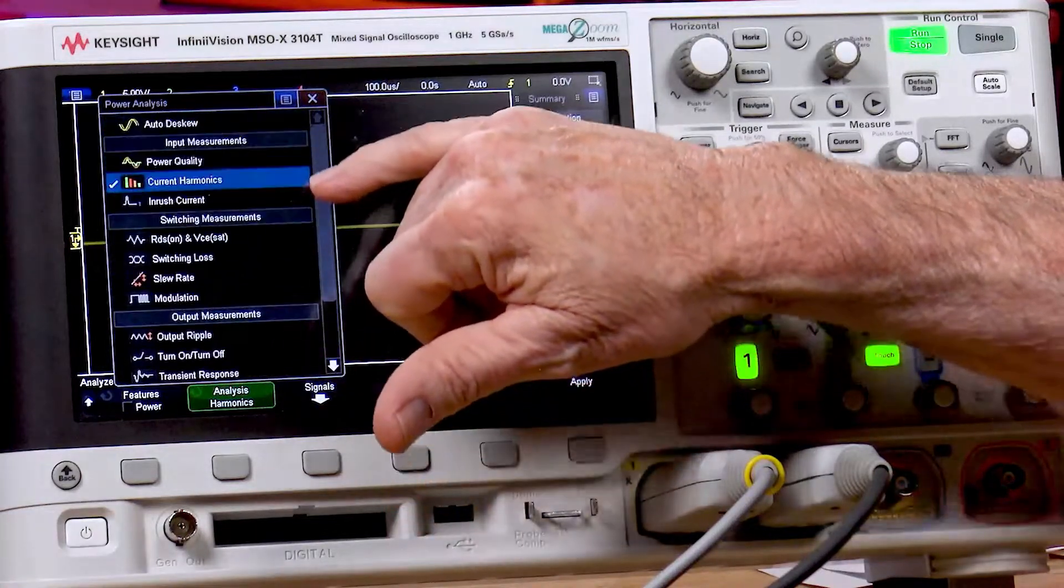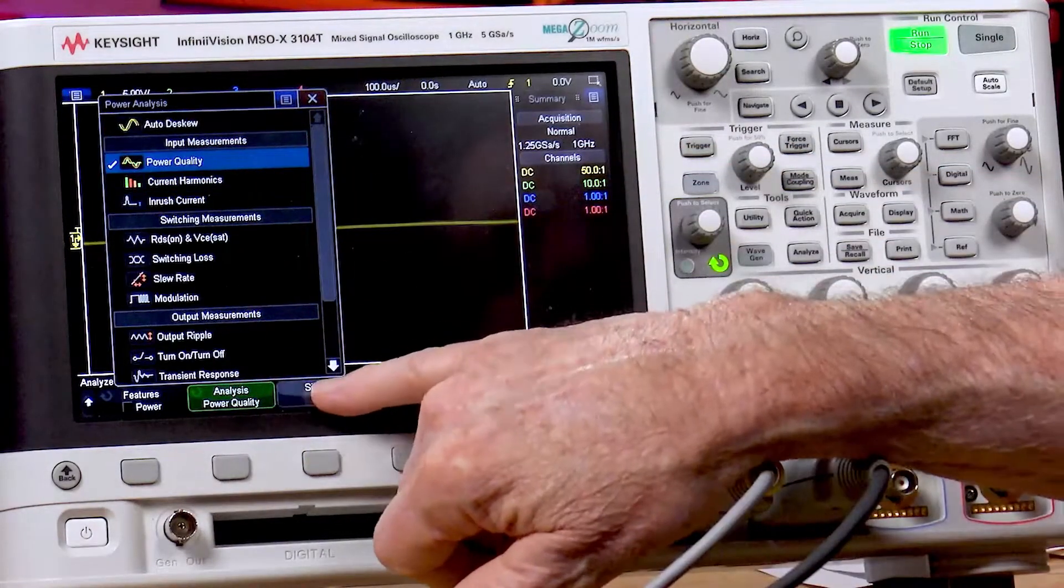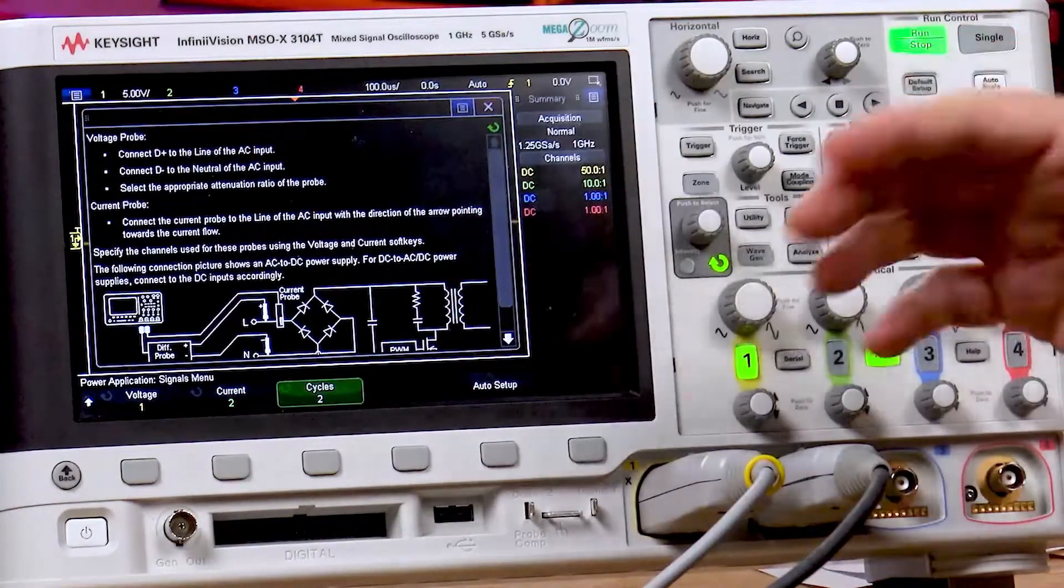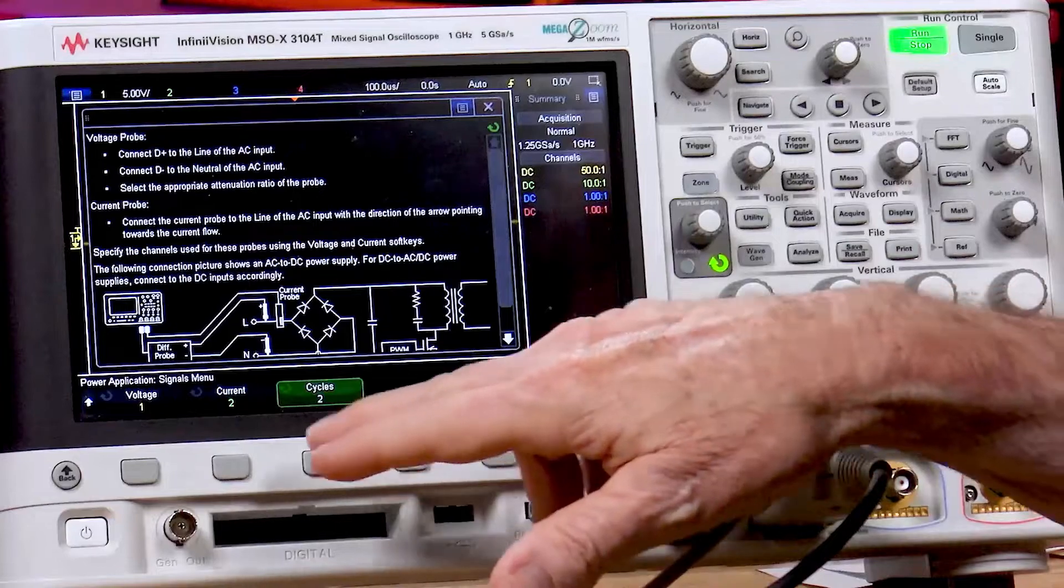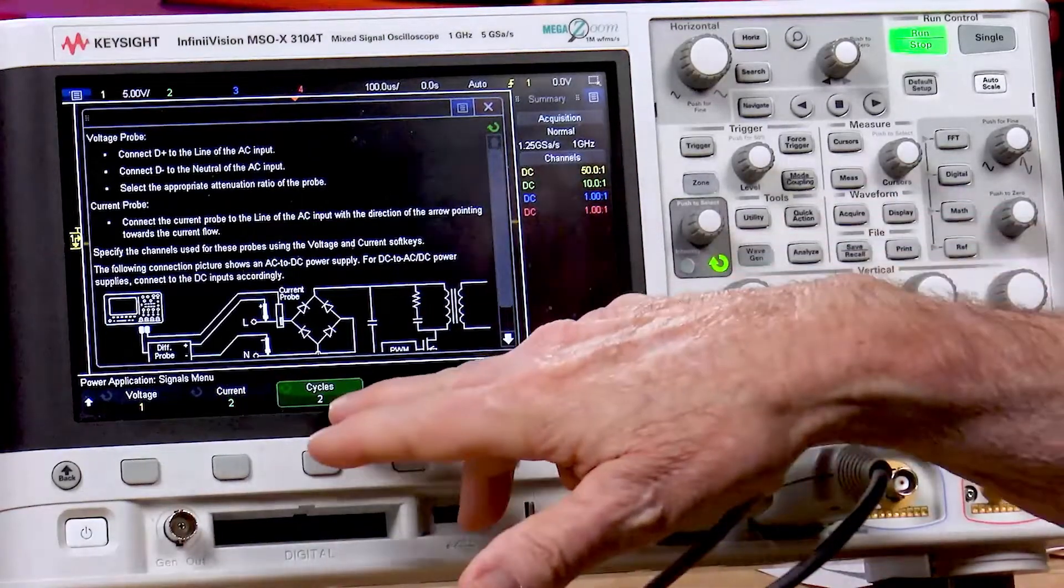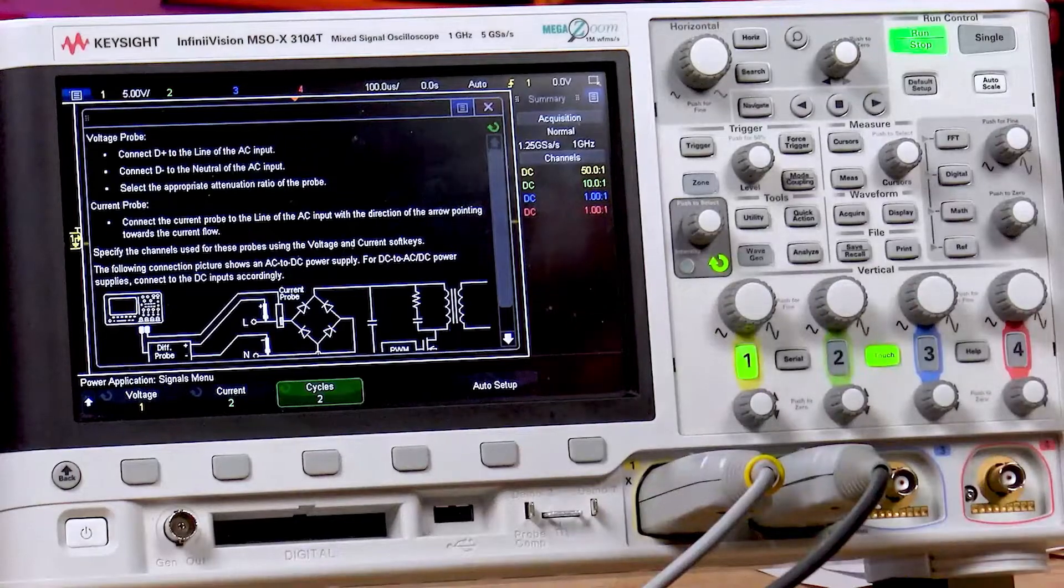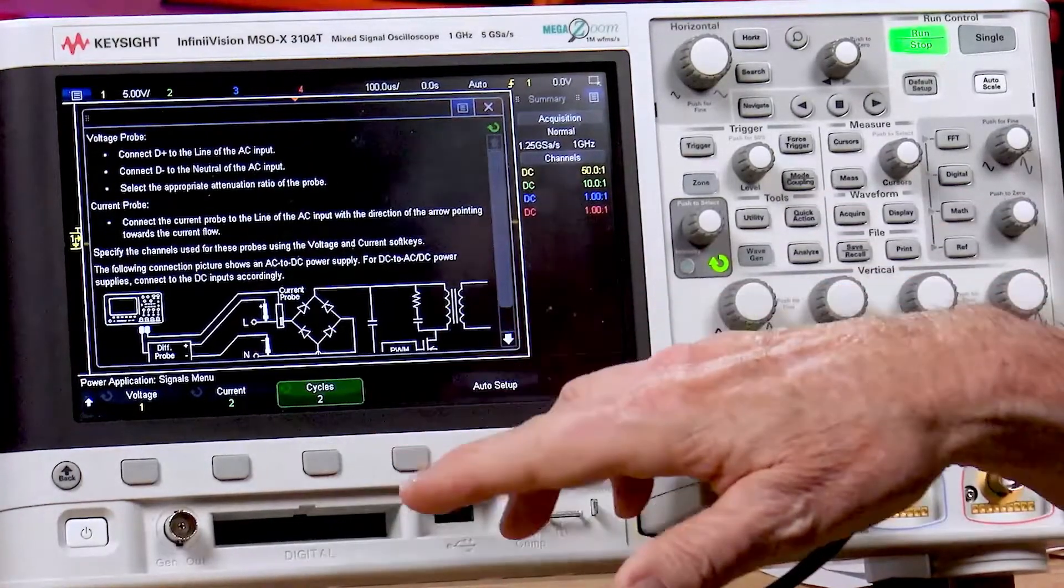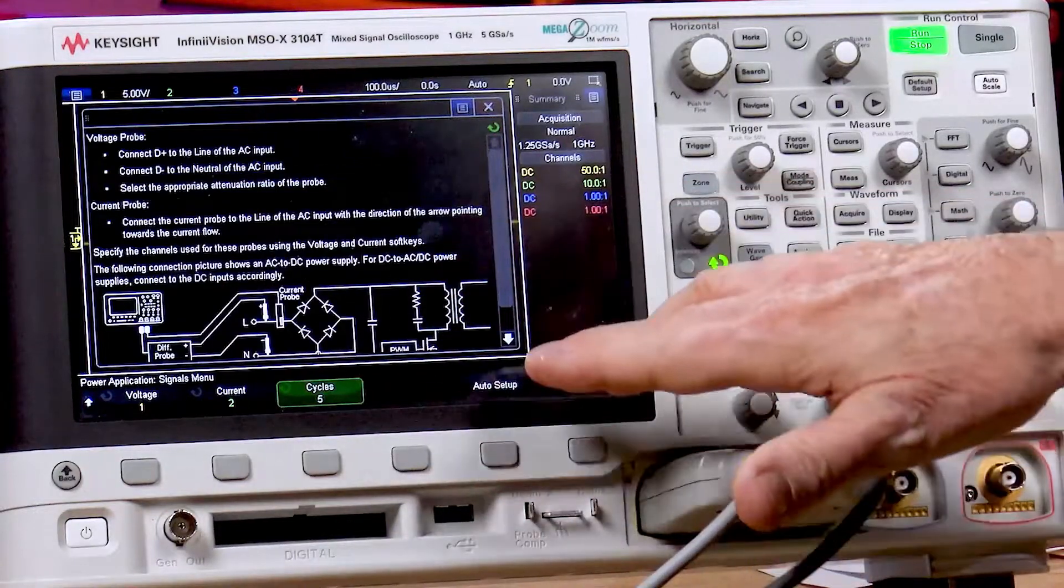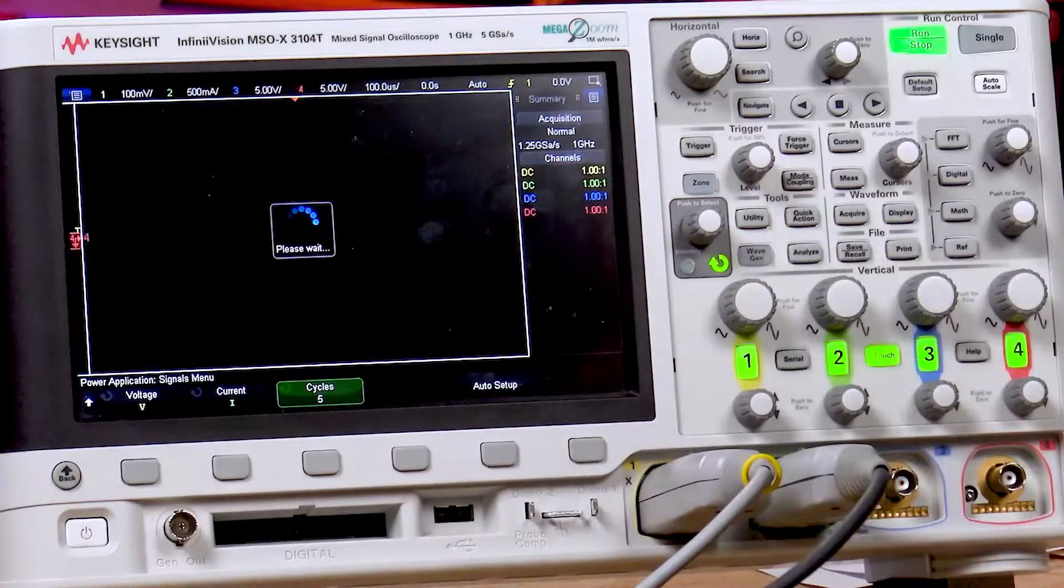Let's go back up here and select Power Quality, go into the Signals menu. It shows you how to connect up to the AC input, and you can assign which probe is voltage, which is current, and select how many cycles you want to perform this measurement on. The default is two, I'm going to change it to five, and then just select Auto Setup.